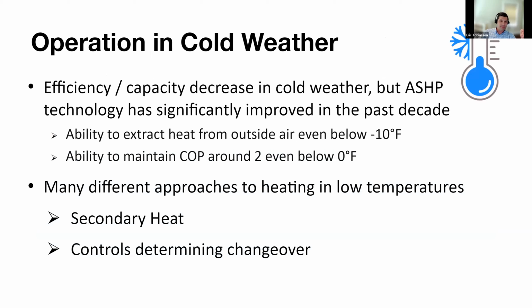So operation in cold weather for a VRF heat pump, basically your efficiency and your capacity are going to decrease because there's just less heat in the atmosphere that you can draw from. Any VRF manufacturer can tell you what your heating capacity would be at lower temperatures, but we're still able to get heat from the outside air even below -10 degrees, and around 0 degrees you're still getting that COP around 2. So again, you're getting more energy out of your system than you're putting into it. If you're looking at heating in low temperatures, there are lots of different approaches. You might have secondary heat. So if your heat pump is just not sized to get heating down to -13, you can keep your natural gas to come on when you see that your space temperature is not being hit by your heat pump. And then you could have controls determining changeover from your heat pump system to your secondary heating system.